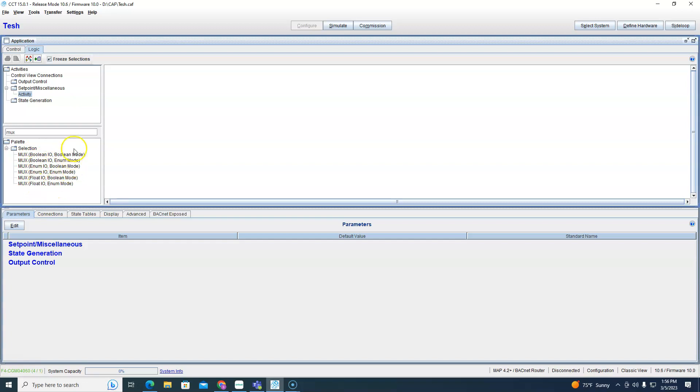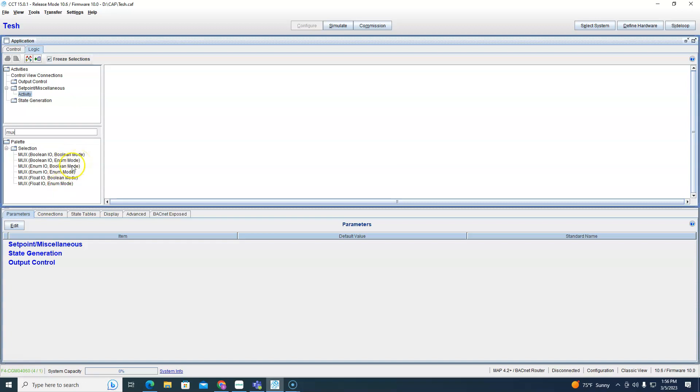And then the next one is the mode. This is what's going to switch it, this is what's going to do all the action. So you have your choice between boolean, which in Johnson Controls is always true false, enum which could be almost anything, and that's it. We don't have a float, you can't do a float mode mux block but you can do a float output mux block.